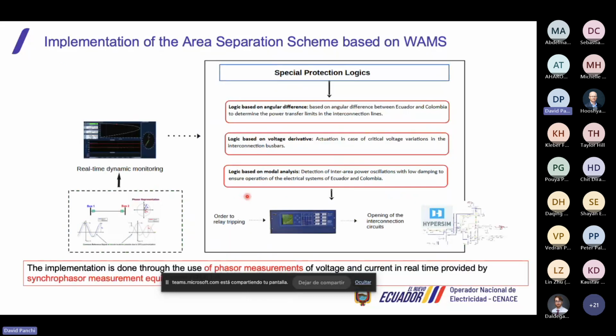So in the next slide, I will show you the implementation of the area separation scheme based on WAMS. The first step we do is define the logics. So we define three logics for the separation. Logic one is based on angular difference. As you know, we can have the angular data only via phasor measurements. So this angular difference is to determine the power transfer limits in the interconnection lines.